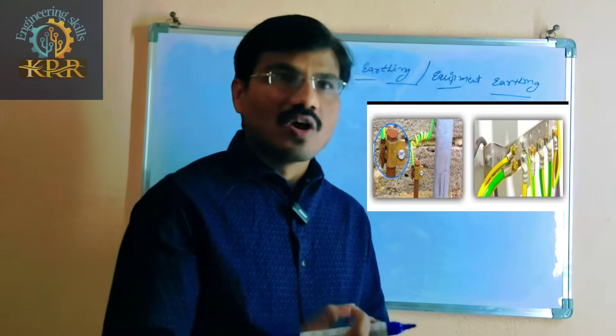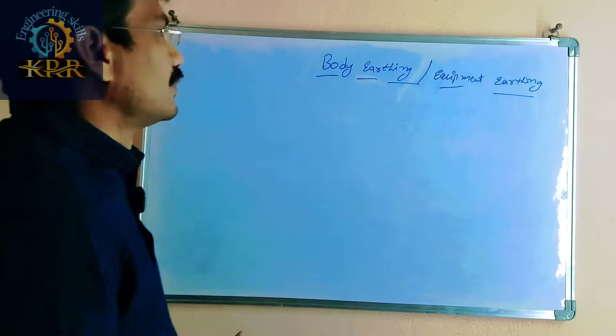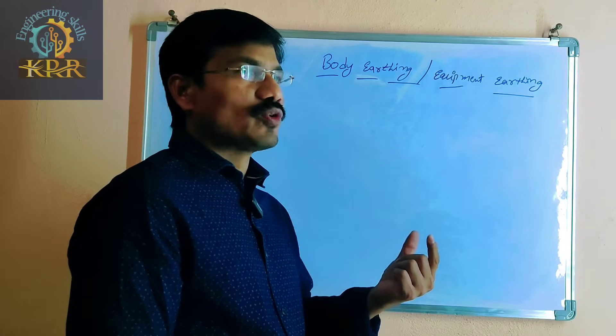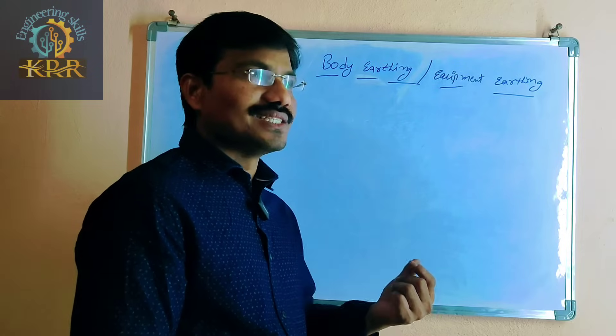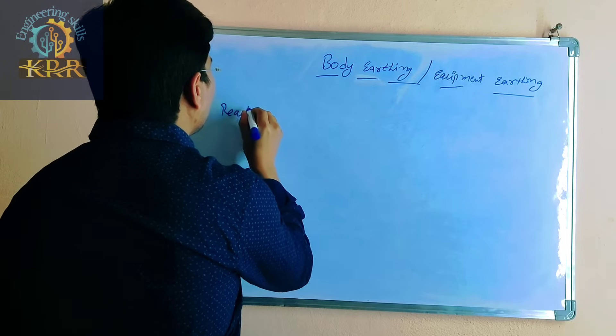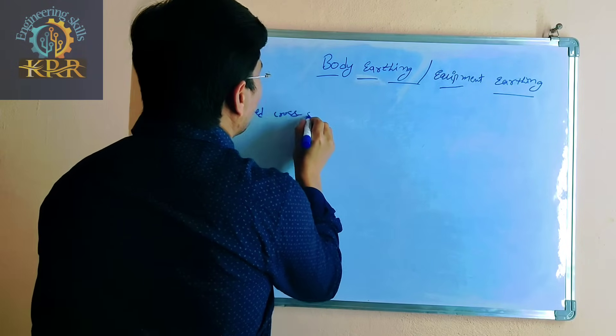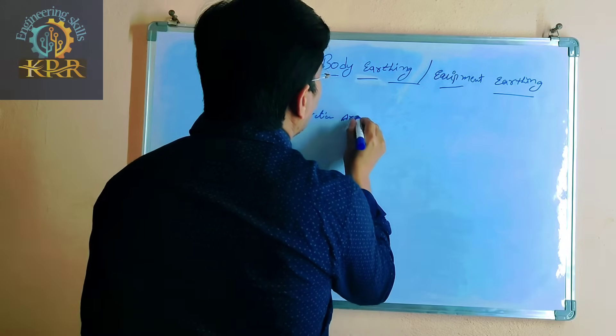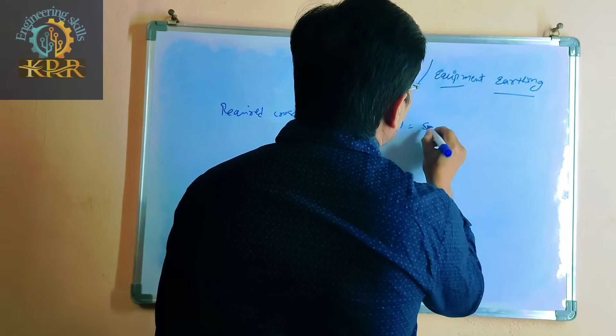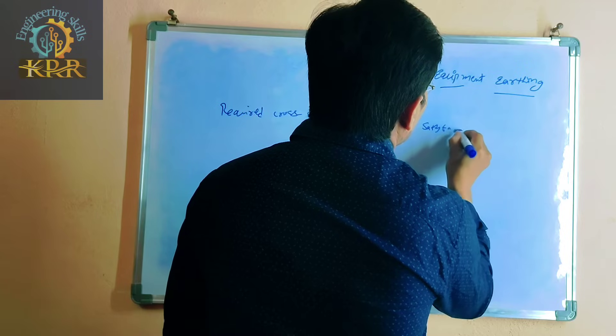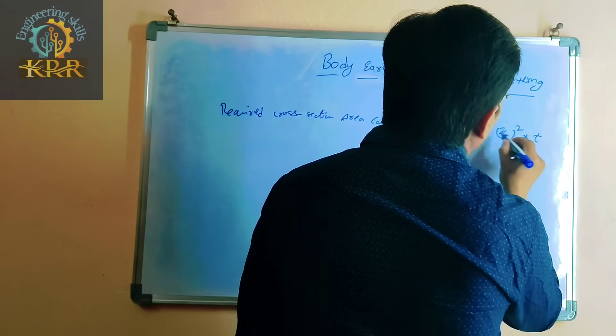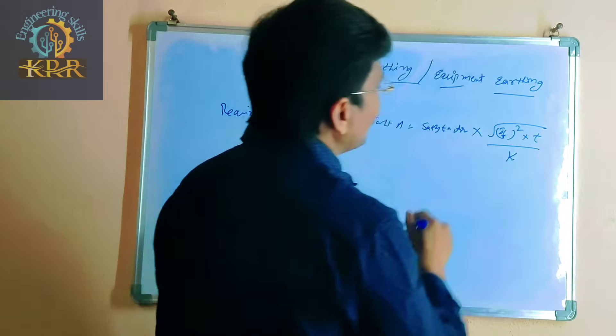How to estimate the required earth wire size? The required cross-sectional area formula is: A equals the safety factor multiplied by the square root of fault current squared multiplied by time, divided by K. This is the formula used to calculate how much earth wire is required.